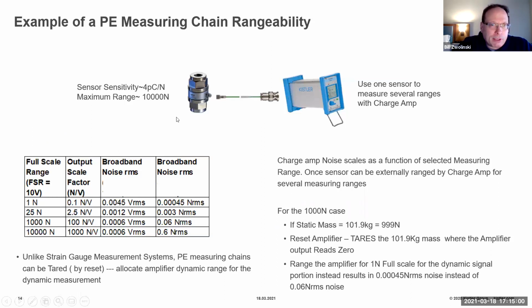Here's a simple example where you have a sensor that's rated for 10 kilonewtons, and you have a charge amp and a cable. In this scenario, you can easily range the measuring chain for 10 kilonewtons or 1 newton. And you can see that the broadband noise actually scales as a function of range. So unlike a strain gauge device, where you would be taking the resolution of a 10 kilonewton sensor, in a piezoelectric device, you take the resolution of whatever range that you set up in the charge amp. Totally different concept, but very powerful. It's almost magical in some ways, people say that to me.